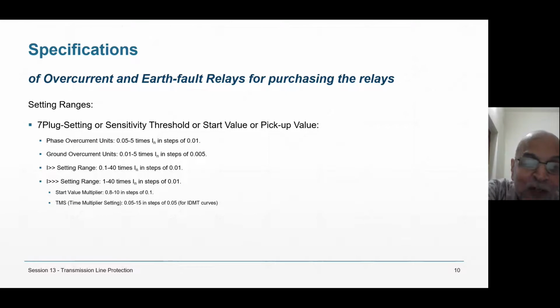But if it is a fault, then it will not be so, because the start value multiplier means 0.8 to 10 times, but a fault is 1 time to 5 times. So the start value multiplier will not act and the relay will operate. The multiplier is 0.05 to 15 as against 0.05 to 1 in steps of 0.05. So these are the setting ranges.